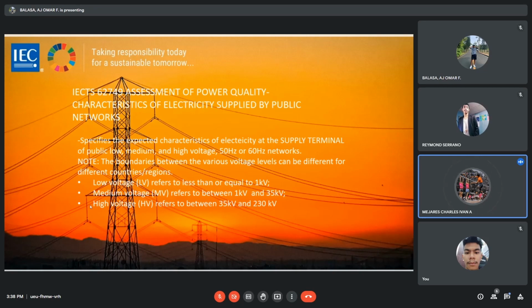Low voltage refers to less than or equal to 1 kilovolt. Medium voltage refers to between 1 kilovolt and 35 kilovolts. High voltage refers to between 35 kilovolts and 230 kilovolts. Note that because of existing network structures in some countries or regions, the boundary between medium and high voltage can be different.